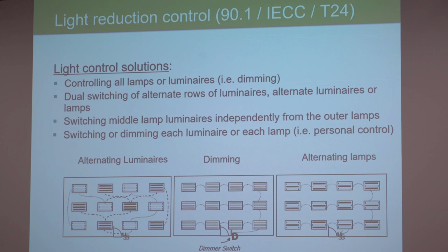So these are the different ways you can meet that requirement. Basically, dimming all the lights complies. You can also do what they call dual level switching or bi-level switching, where you switch alternate luminaires off, or alternate rows of luminaires, or alternate lamps in a luminaire off. Preferably, the ideal way to do it is to make sure that if you're doing multi-level lighting, the illumination is even throughout the space, so you're not going to get a dark spot, light spot, dark spot, light spot.